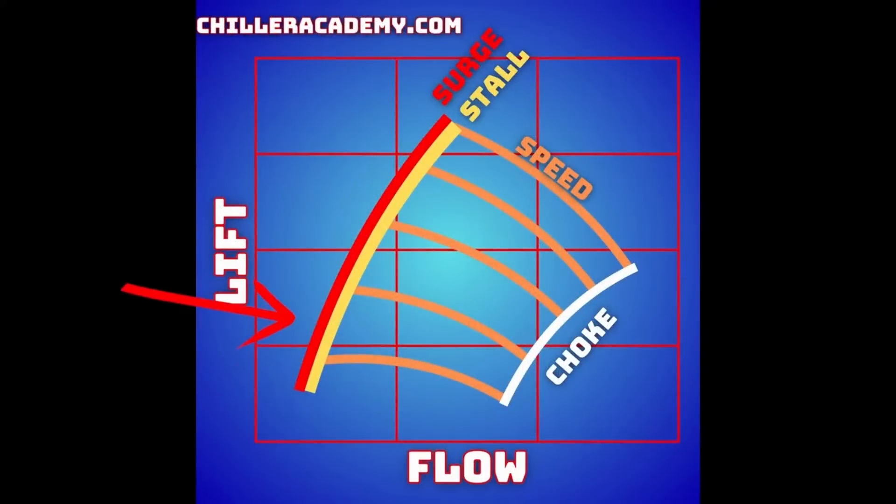how much lift we can achieve with that impeller without surging also lowers. So when we've got a minimal load, our surge potential is very, very low compared to if we were at full load where we had to ramp the compressor to a higher speed — we could run up there all day with lots of headroom to operate. But when we get down into the lower load state, that is not true. Our flow rate significantly reduces through the compressor, which pushes us against that surge boundary.